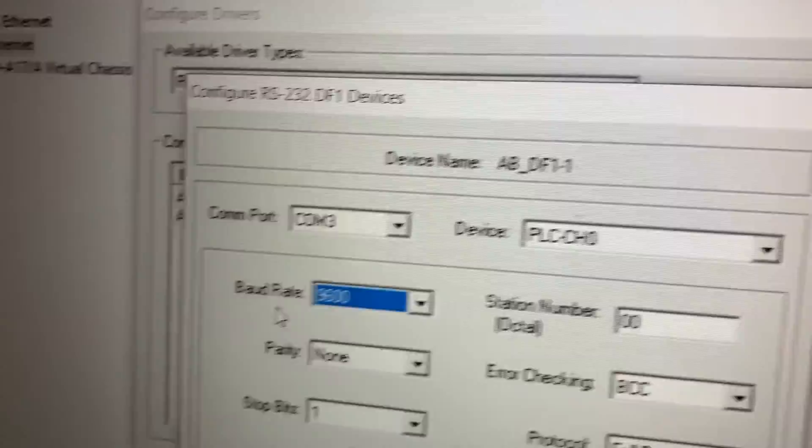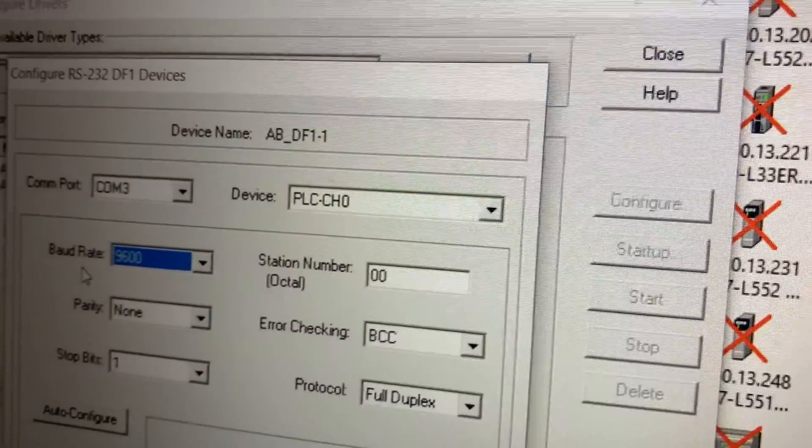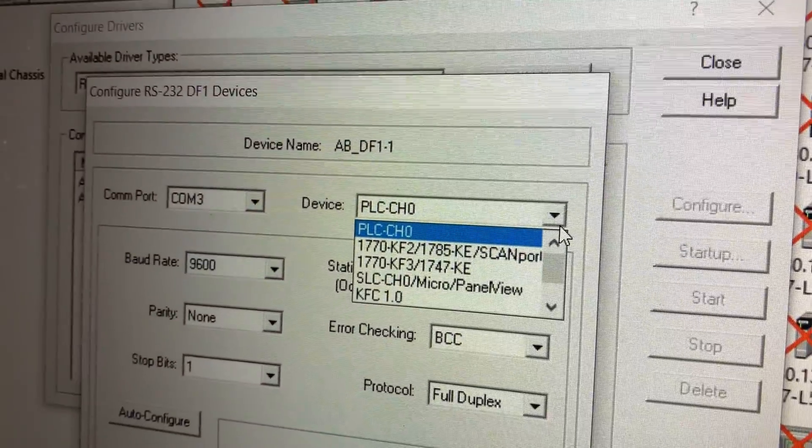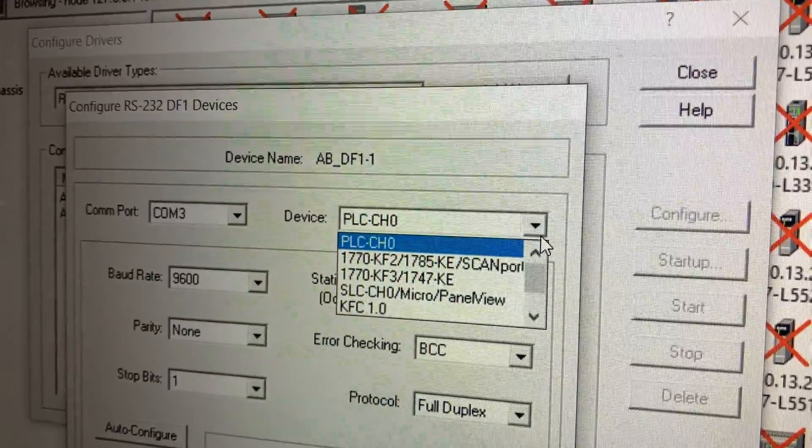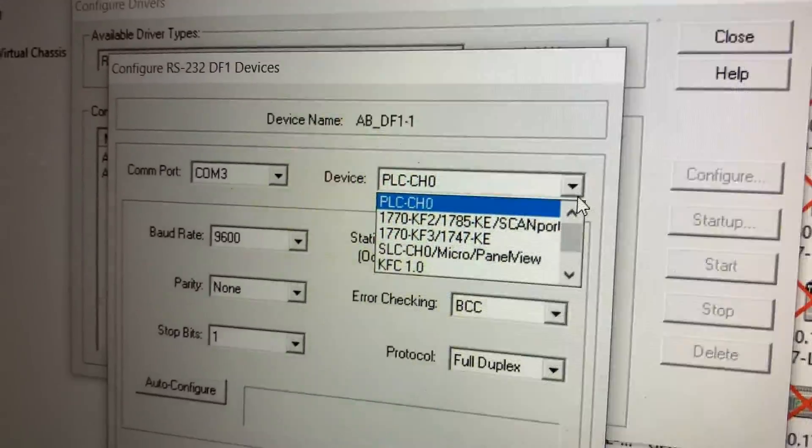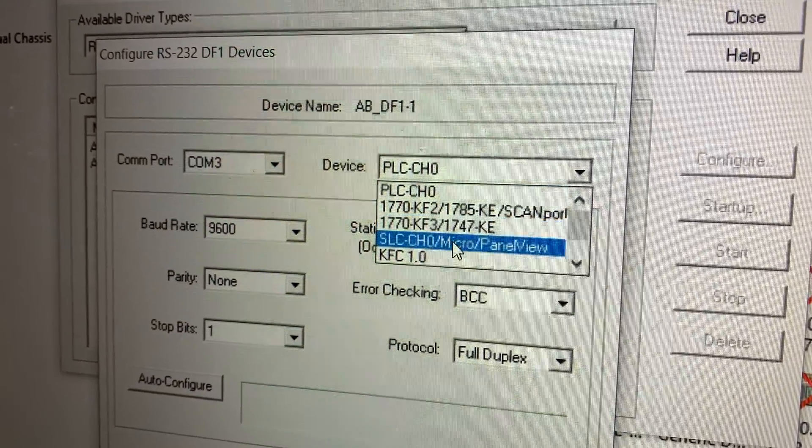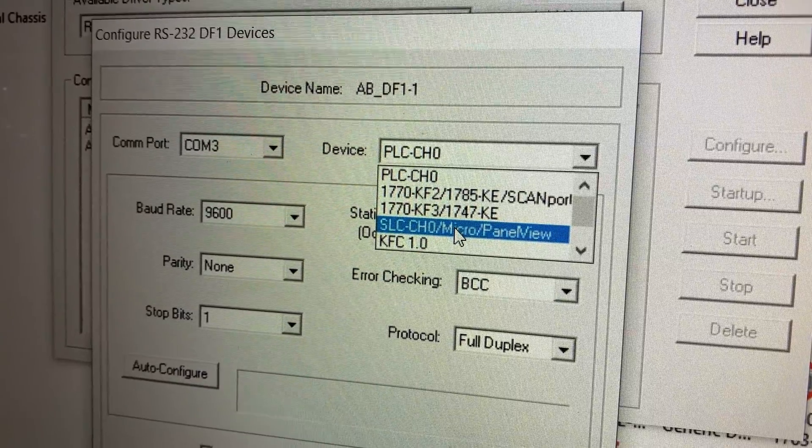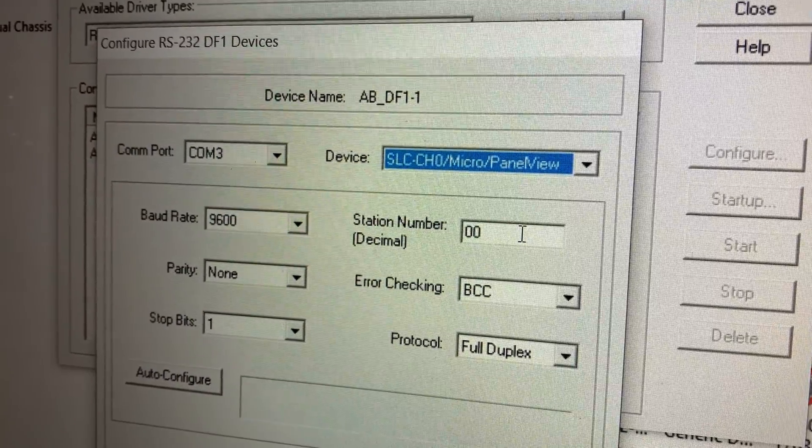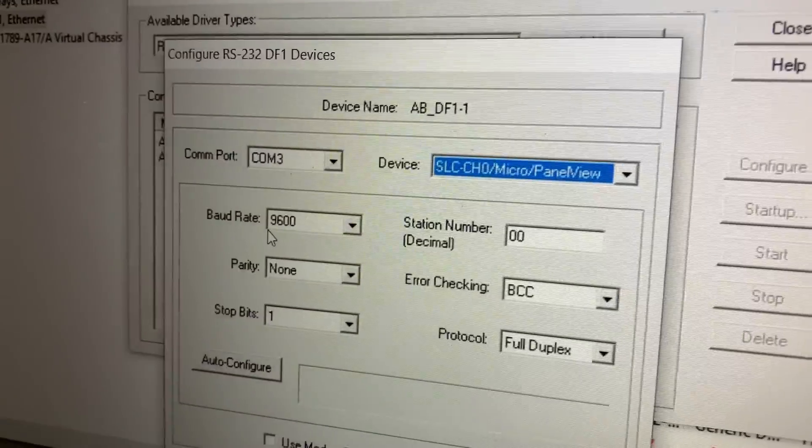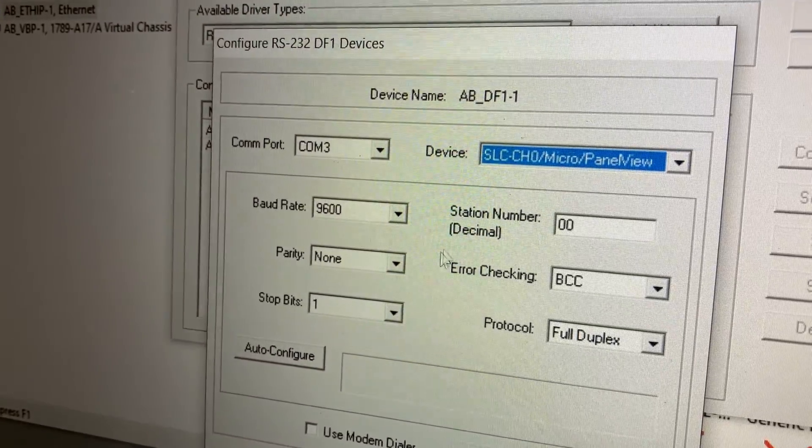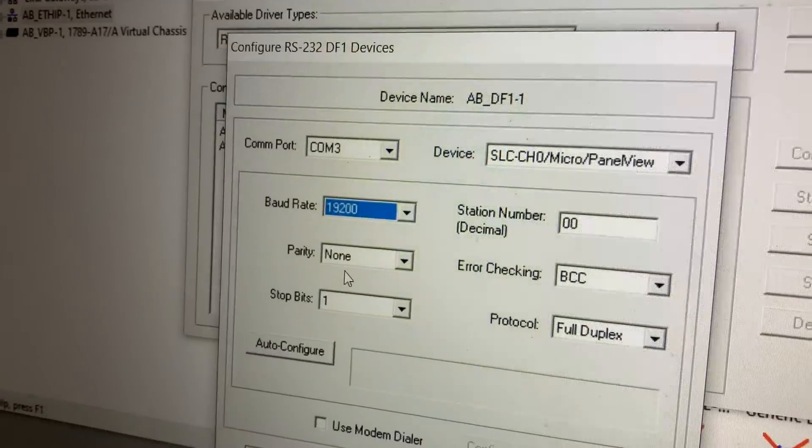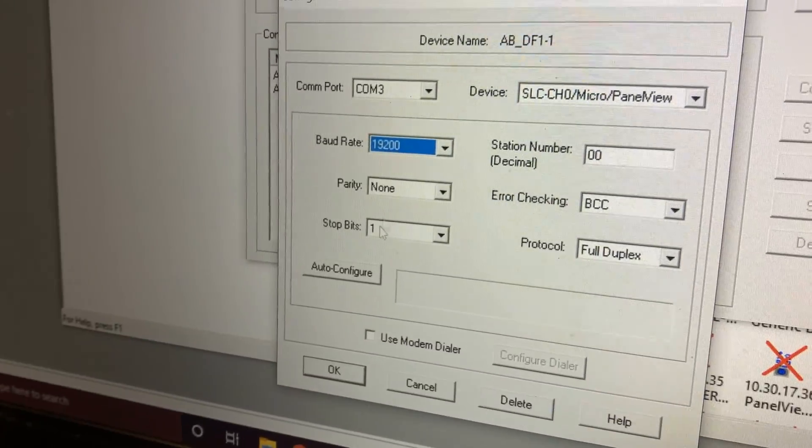After you've got your COM port set, we're going to go to our device. This is very important. If you pick the wrong one, your laptop will blow up. I'm just kidding. So go to SLC-CH0, you see it says PanelView on the end. Bingo bango, select that guy. Then we're going to go to our baud rate, put that as 19.2 to match our settings from the PanelView, and then hit Auto Configure.